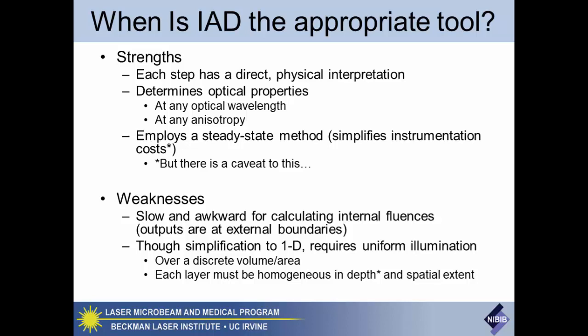Yeah, and I think because they are so different, that's what makes it useful. Because if you can get agreement between those two systems, the likelihood of that happening by random chance is very low. So typically when we fabricate different tissue-simulating phantoms, particularly calibration phantoms for systems, we will use both. We'll make a thick phantom to be measured on reflectance-based instruments, and then several thin samples at different thicknesses for the inverse adding-doubling. So typically for any one phantom, we would have 3 different thicknesses.